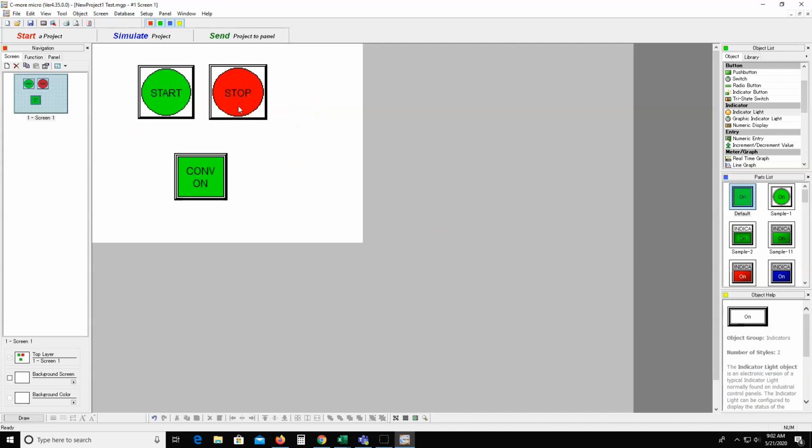So again, these are virtual buttons. They are not physically tied to the PLC, but when we connect the HMI that displays this to the PLC, pressing this button will write to the table in the PLC. And pressing this virtual button will put a 1 in B3, file area 0, word 0, bit 0. This will do the same for B3, file area 0, word 0, bit 1. And those will have to be incorporated into your program.